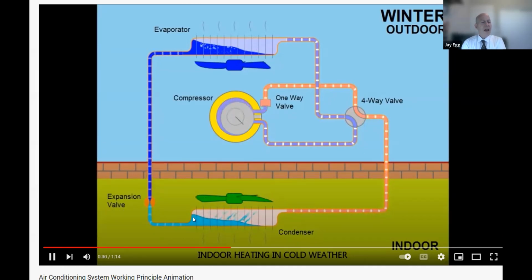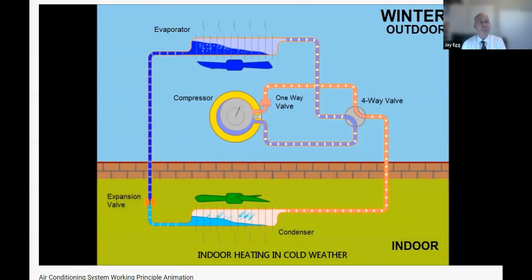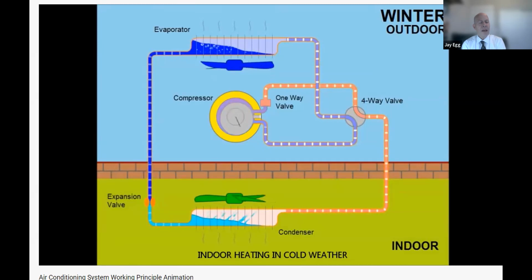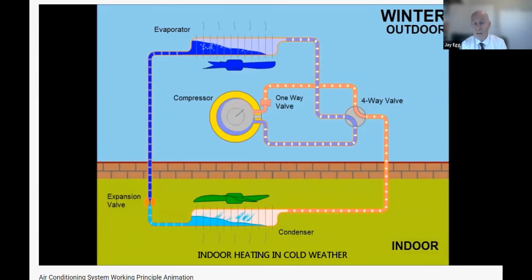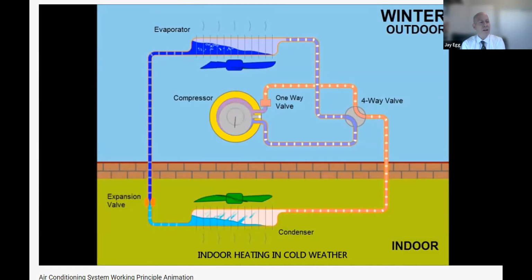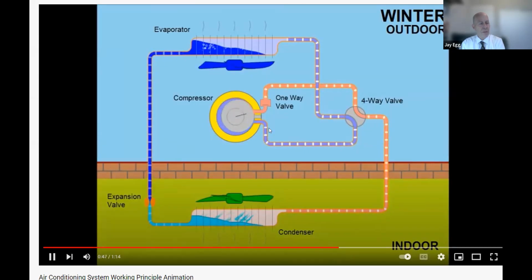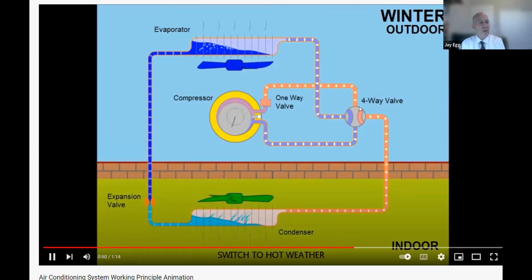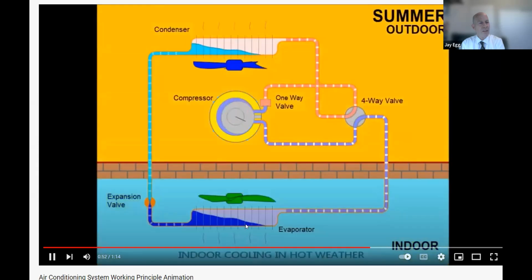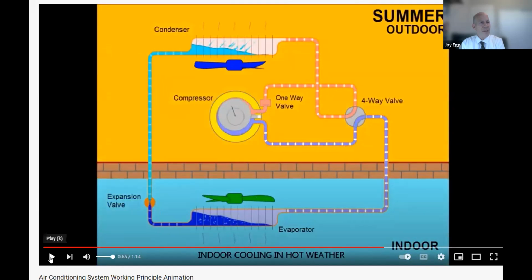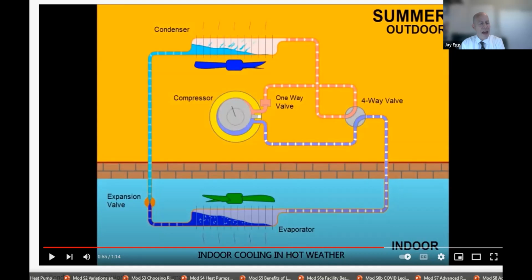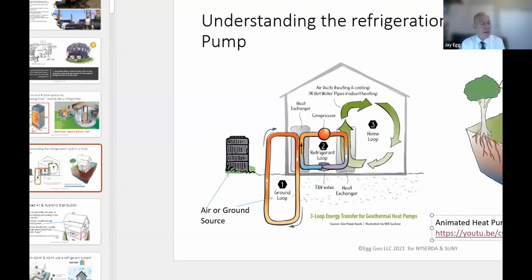And that's the beauty of a heat pump piece of equipment in providing heating and cooling. It is not a heat burning device. It doesn't burn electricity to make heat. Rather, it uses electricity to run a pump, this compressor, which pumps heat. And now it's switching from winter to summer again. You can see that, to move heat from outdoor to indoor and from indoor to outdoor. And that is what's happening right here.